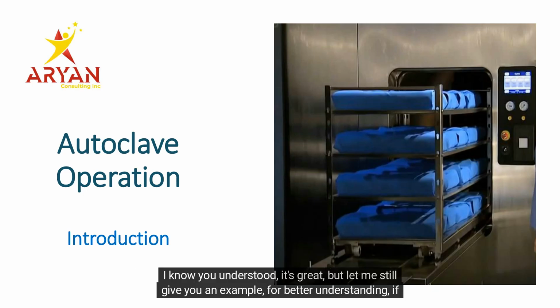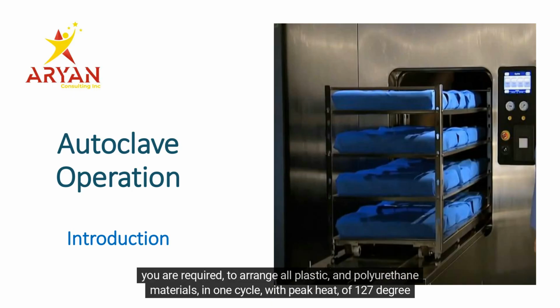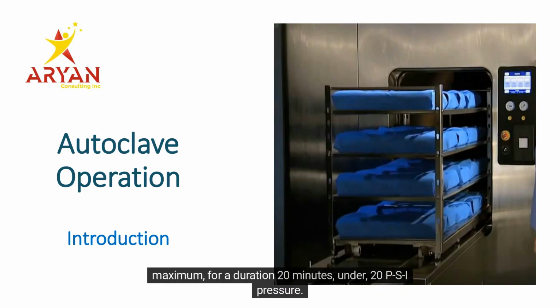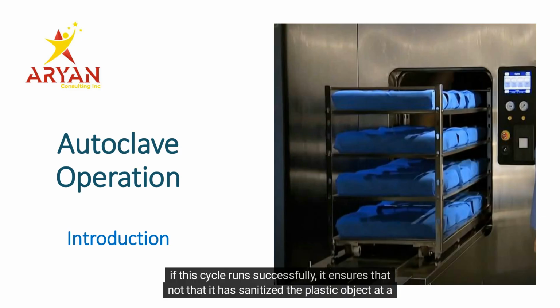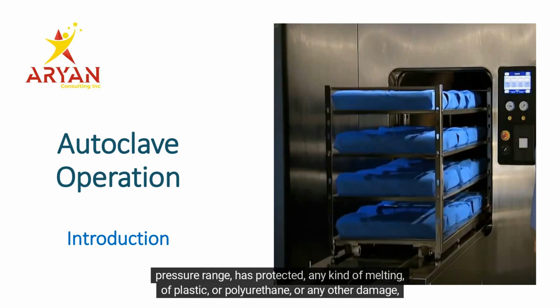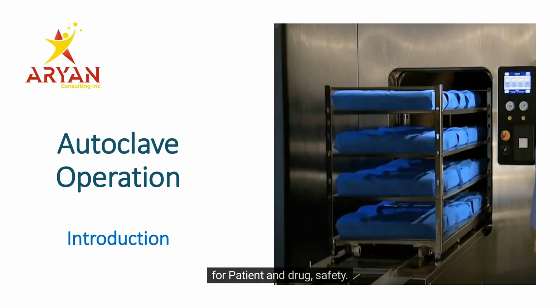I know you understood it, it's great. But let me still give you an example for better understanding. If you are required to sterilize all plastic and polyurethane materials in one cycle with peak heat of 127 degrees maximum for a duration of 20 minutes under 20 psi pressure. If this cycle runs successfully, it ensures not only that it has sanitized the plastic object at a peak temperature that the plastic object can sustain, but it was also made sure that the time duration and pressure range have protected against any kind of melting of plastic or polyurethane or any other damage, for patient and drug safety.